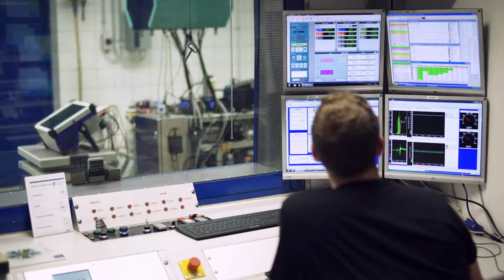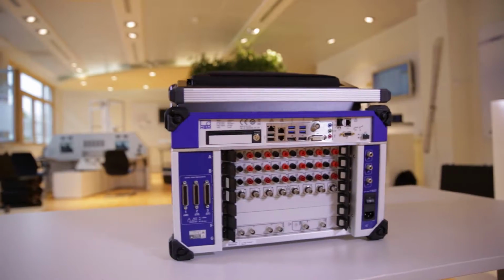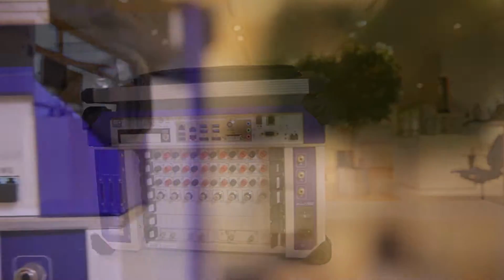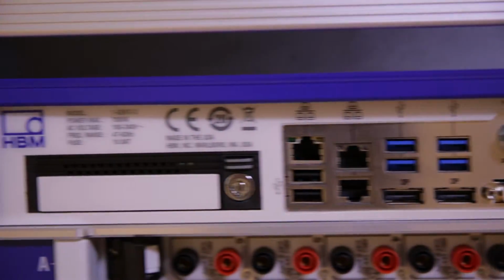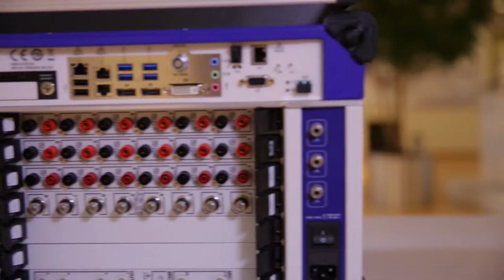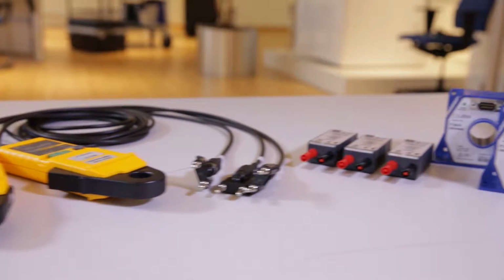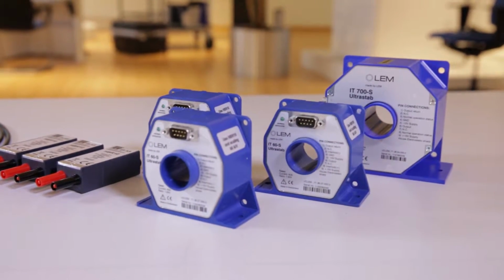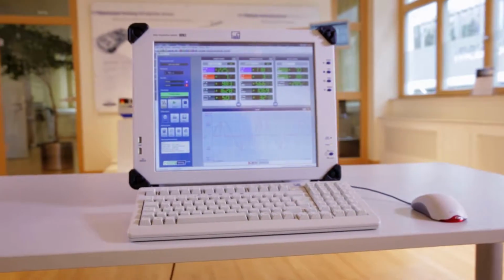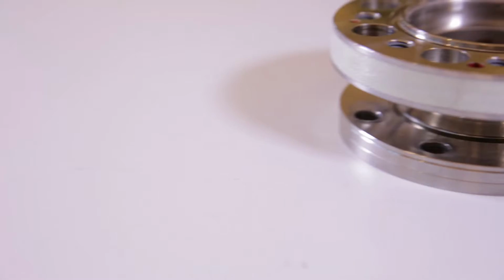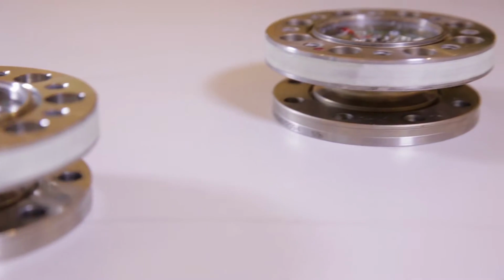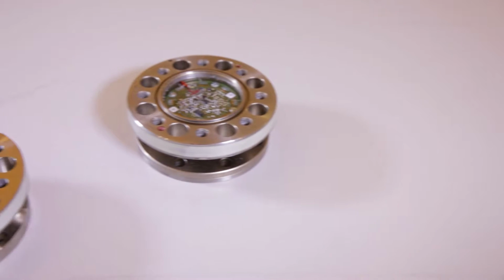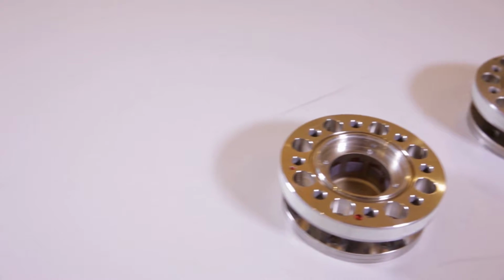But beyond this, it also stores continuous raw data for verification and detailed analysis, such as space vector or DQ0 transformation. The modular DAQ system for 12 to 42 voltage and current channels meets even the most complex test requirements for electric drives. It offers direct inputs up to ±1000 volts, easy connection of current clamps or current transformers, and a sample rate of 2 megasamples per second per channel to catch high-frequency components in the signals. Combined with one or more world-class HBM torque flanges for torque, angle, and speed measurement, it forms the base of the next generation of test instruments for electric drives.